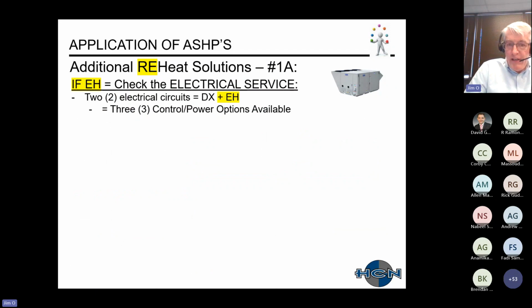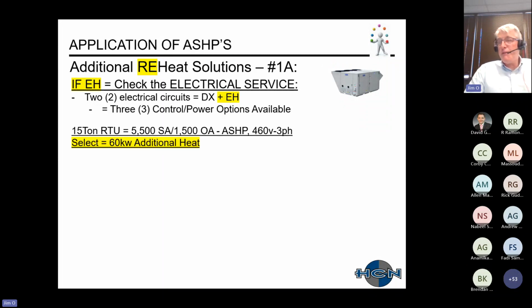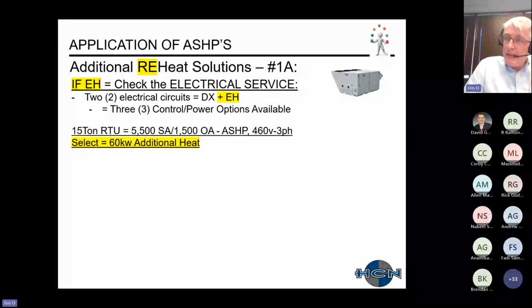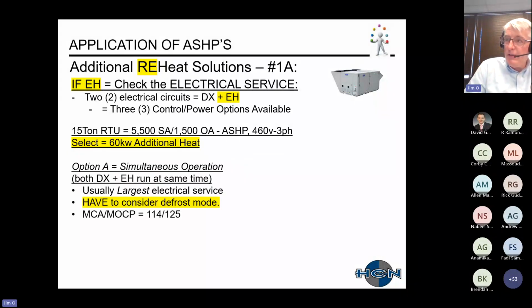Now, if you have an electric heater, you have to check your electrical circuit. Just realize that you have two electrical circuits operating at the same time: your refrigeration system and your electric heater. With the unit, you have three different control sequence of operation and power options available. So, back to my 15-ton selection with that 60 kW heater.